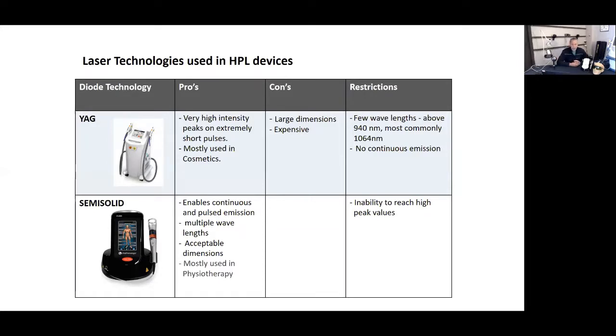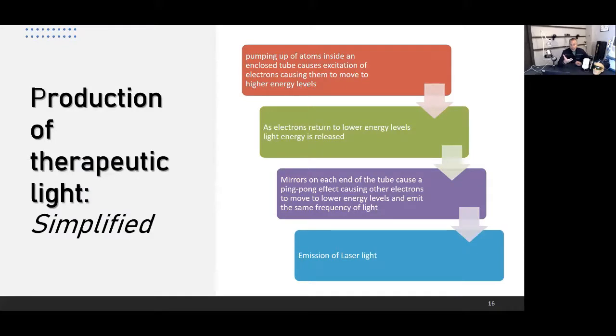A lot of those were originally developed as higher power lasers, not specifically for the therapeutic market, but they were governed down into our world, using a governor or a duty cycle for the most part. We'll get into why, even though it has more power, it has more to do with wavelength on your depth of penetration. Wavelength, let me repeat that, wavelength on your depth of penetration, most important.